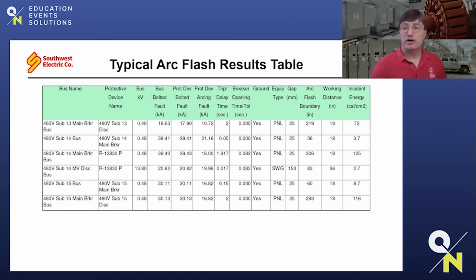So we're going to do a little exercise. I want you to help me determine what are the items, what are the buses on this little section of a table that are of the most interest. This is actually from an arc flash assessment. These are true values that were recorded and calculated. So tell me what the three highest incident energy levels, again, that far right column, that you would want to look at first. Yes, obviously they're going to be the ones that are above 40 calories per square centimeter.